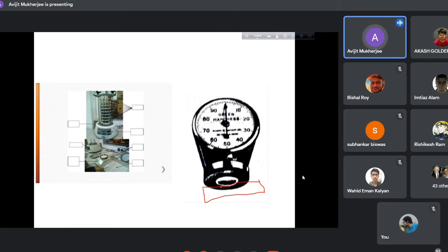Obviously the harder mass will be indented to a lesser extent, and the softer will be indented to a greater extent. The radius of curvature you would have to measure, but you need not measure, because the device is already calibrated. One pointer will rotate, and this rotation reflects the radius of curvature, which depends on the pressure.